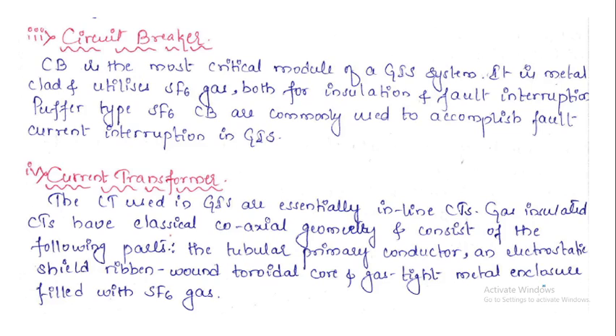Then we have the current transformer. The current transformers used in a GIS are essentially inline CTs. They are directly connected to the line. Gas insulated CTs have a classical coaxial geometry and consist of the following parts: a tubular primary conductor, an electrostatic shield, a ribbon wound toroidal core, and a gas tight metal enclosure filled with SF6 gas. So this is about the current transformer.